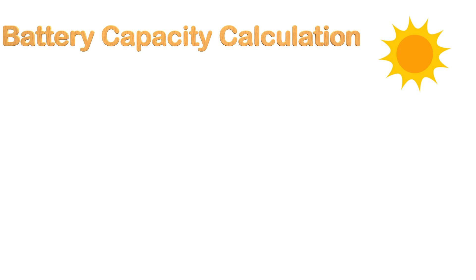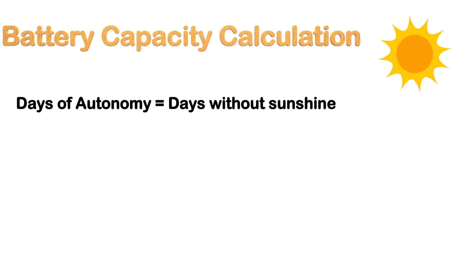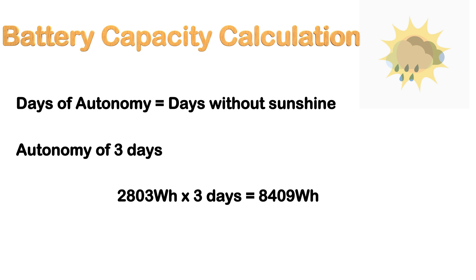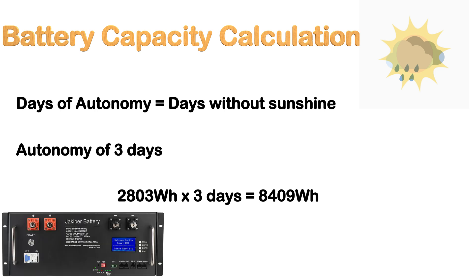In step two, we must decide how many days of autonomy we want. A good measure is about three days, so you can still power your loads when the sun is not shining or it's raining. Remember, the more autonomous days you have, the more batteries you will need. We totaled our loads at 2,803 watt-hours per day, so multiplying by three days gives us 8,409 watt-hours.